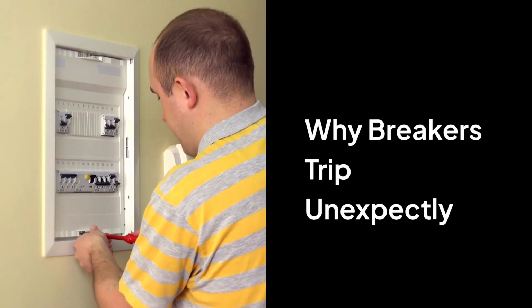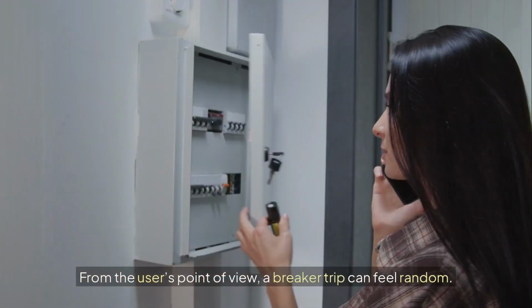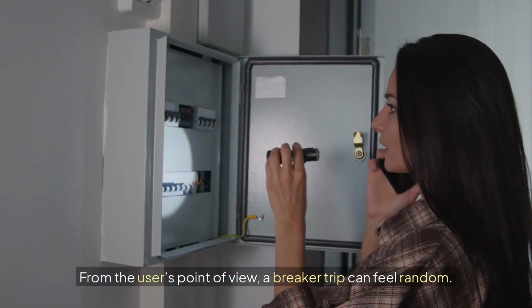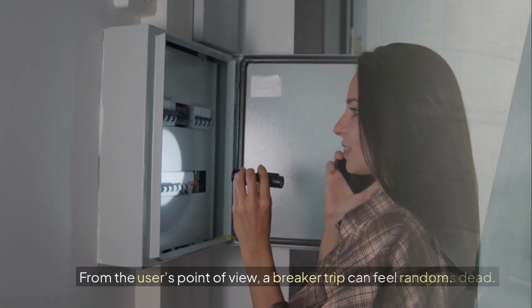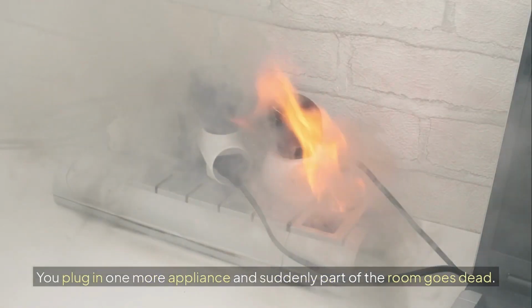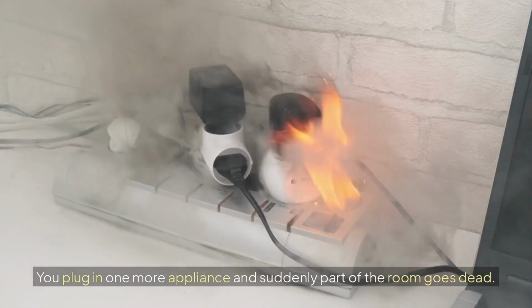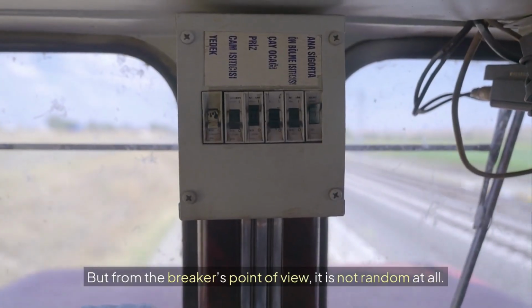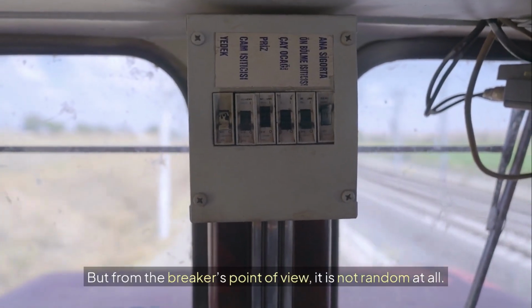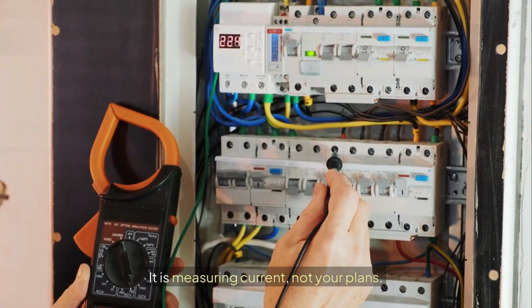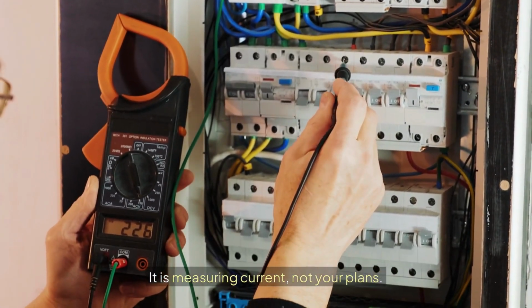Why a breaker trips even when nothing feels wrong from the user's point of view? A breaker trip can feel random. You plug in one more appliance and suddenly part of the room goes dead. But from the breaker's point of view, it is not random at all. It is measuring current, not your plans.